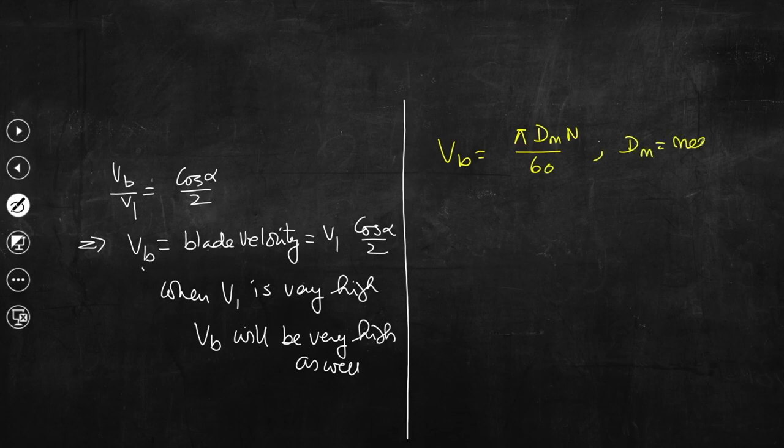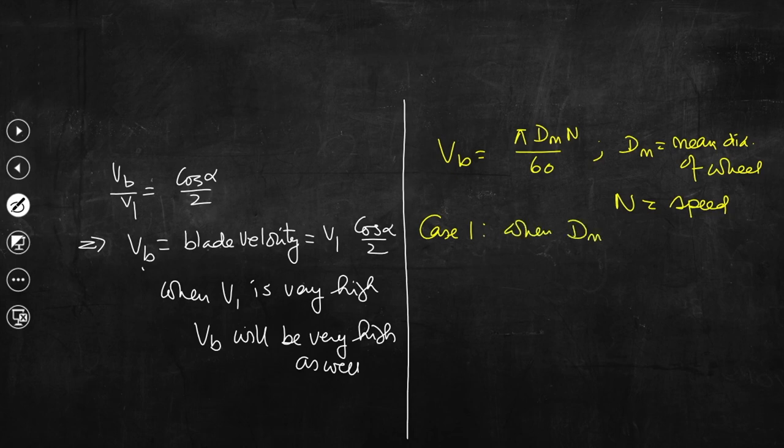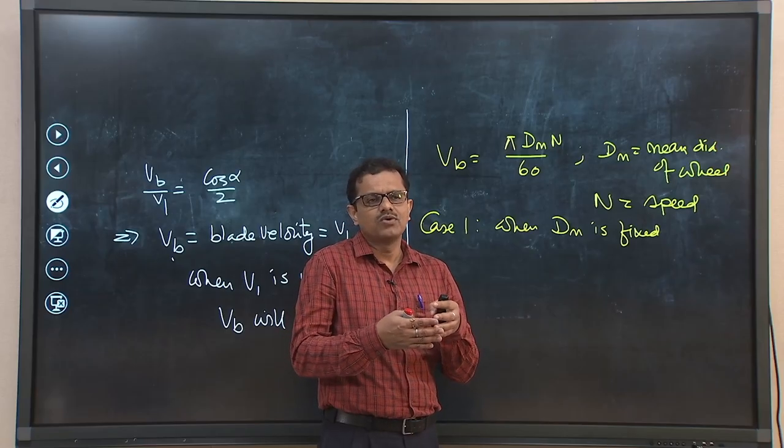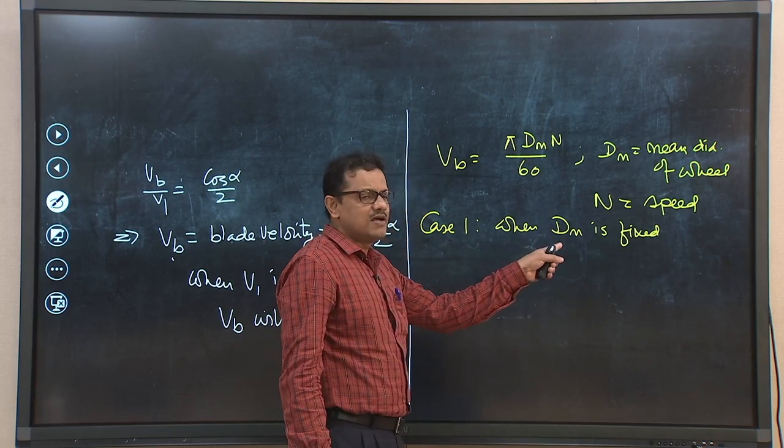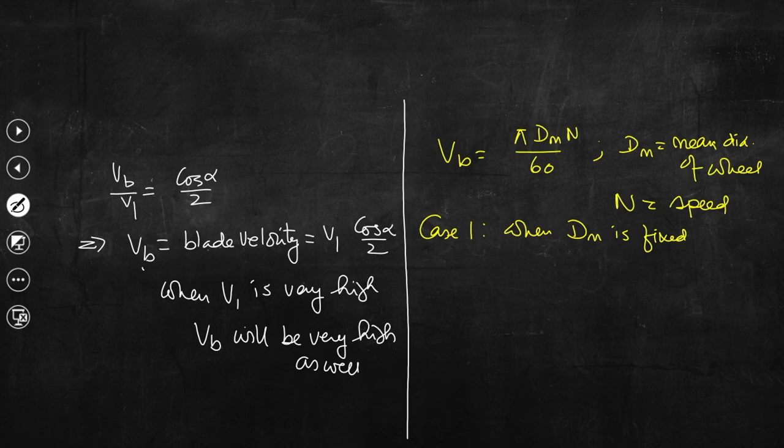Dm is the mean diameter of the wheel, and n is the speed of the wheel. So, there are two possibilities to accommodate such a high V_B. Case 1: when Dm is fixed. Dm we cannot increase beyond a particular value to meet the space constraint, because when you are installing a turbine in a power plant, the turbine house has a space constraint.